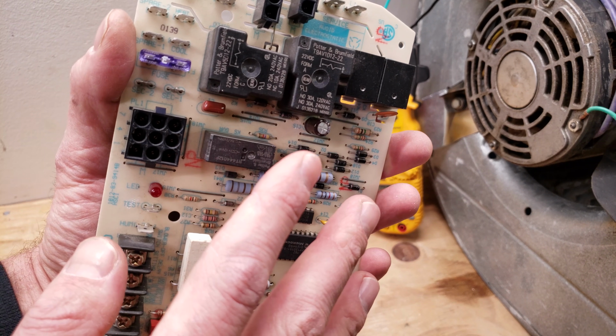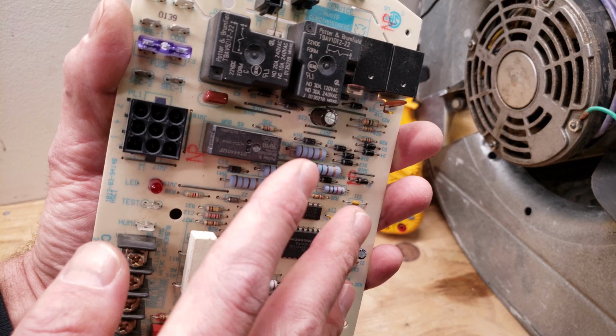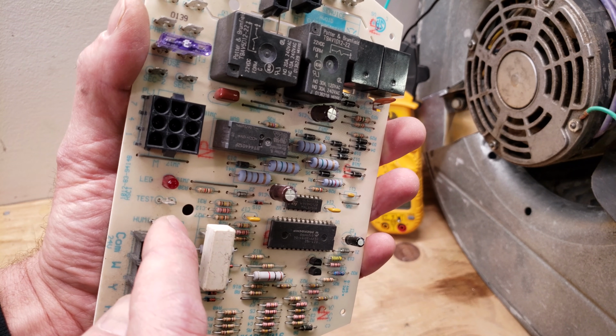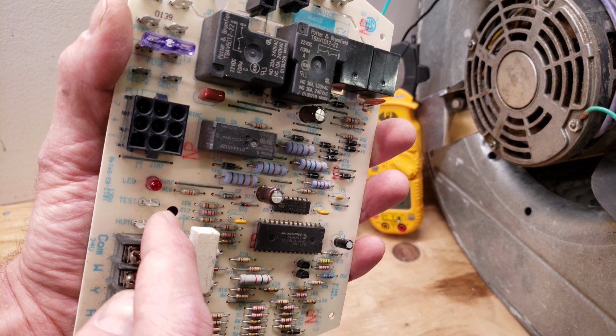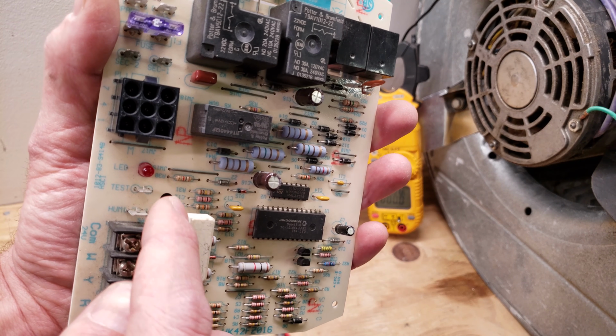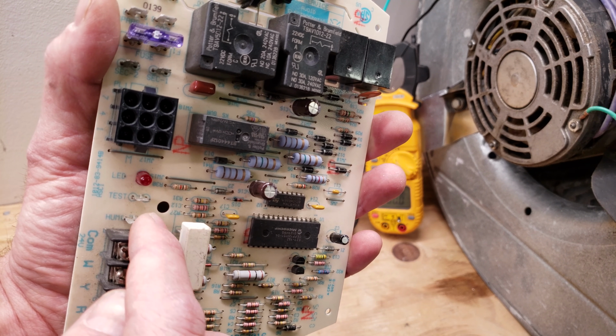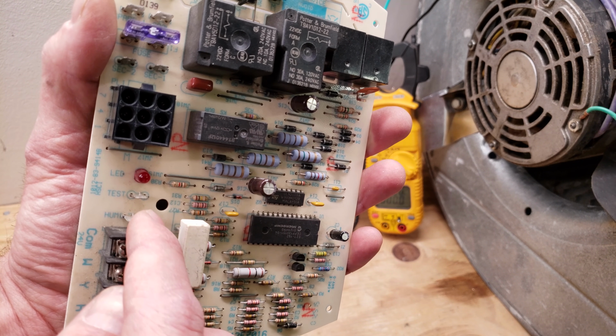So a lot of times these are already built on the control board, and the nice thing about the HUM tap on the control board is it's only going to send the 24 volts out of this tap during furnace mode, during heating mode. So it's not going to be sending that just during fan mode or just during air conditioning mode.